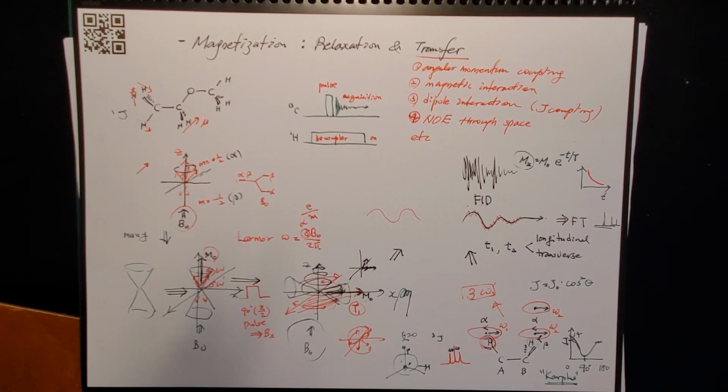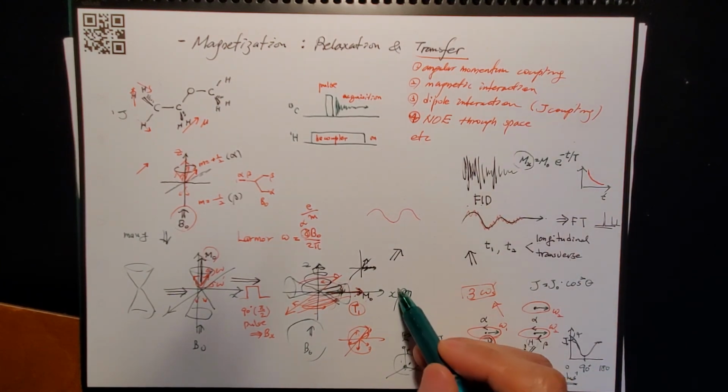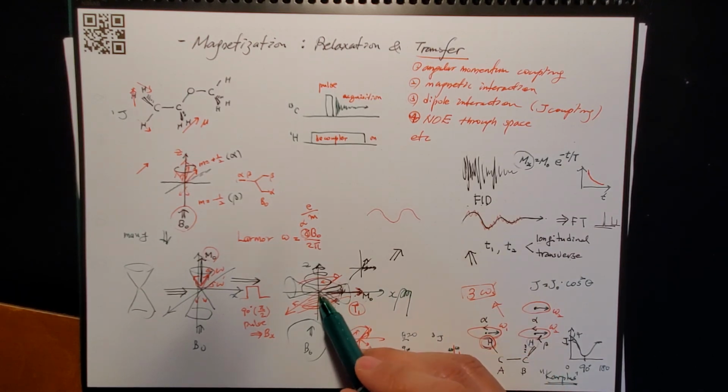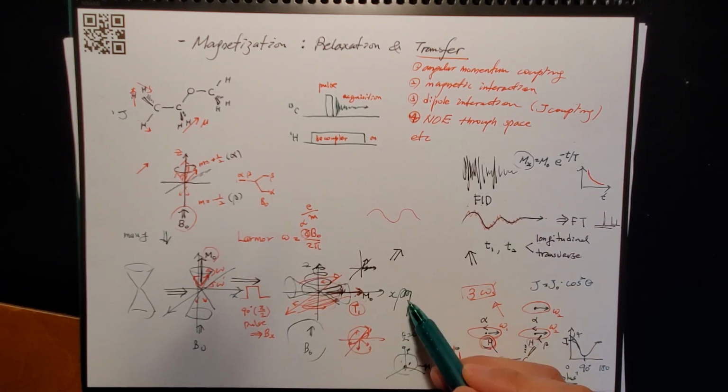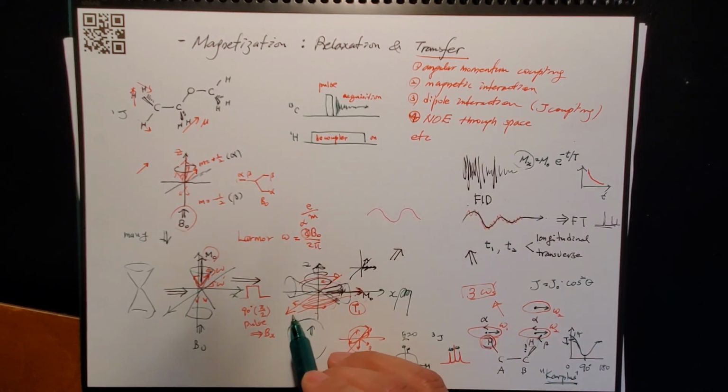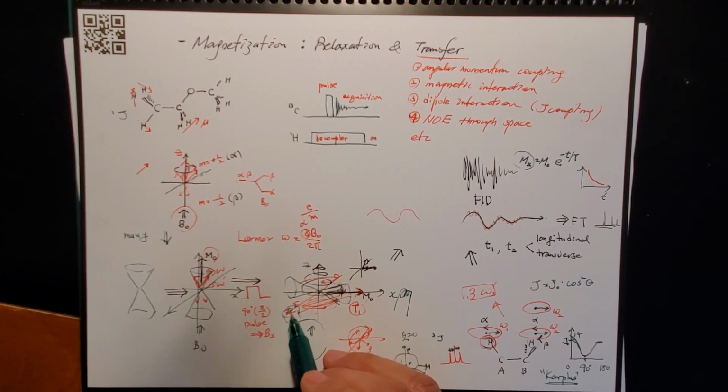But then how do you remove the interaction? The key idea on the instrumental side is you have your detector like this for the carbon-13 frequency. Then you have your signal, the pulse signal, for the coil that generates the pulse for hydrogen.